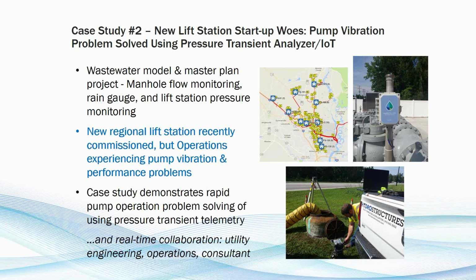And during the summer, a new regional pump station was commissioned, and operations was having a really tough time with pump vibration, and was just struggling. The design consultant wasn't quite sure what was going on either. And so operations was out there in the field constantly trying to change some of the pump operation. They thought it might be airlock, and we're running the larger pumps once a day and trying some different things, but they really just weren't getting very far. The problem wasn't getting resolved.